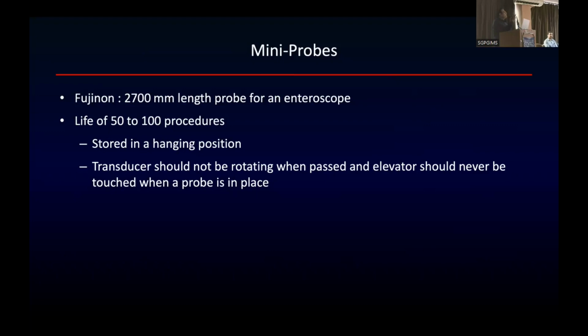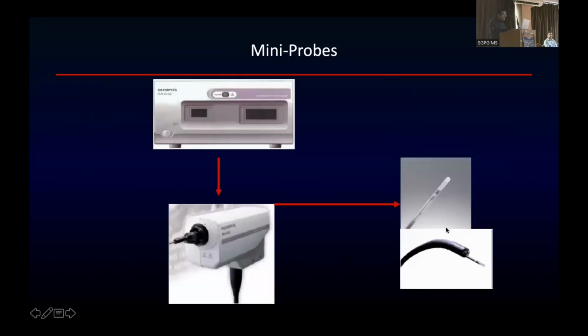You will lose the mini probe straight away if you don't follow this. That is, unless it reaches the particular site where you want to image, you should not be using the elevator with the mini probe. Otherwise, you will damage the mini probe. This is how it looks. So this is what the mini probe is. It comes out through the channel of the scope, and this is the motor driving unit of the mini probe, which is needed in addition to the processor that you already have.